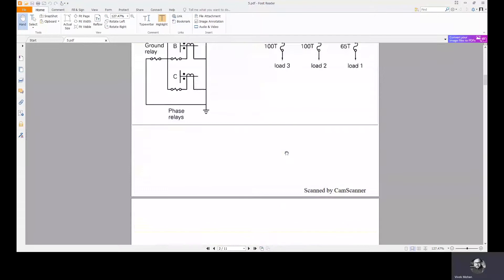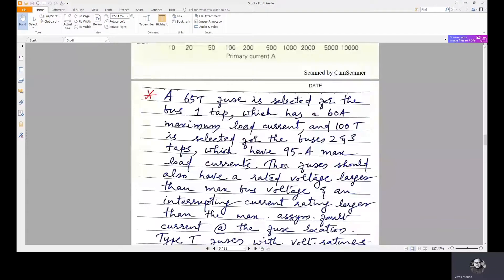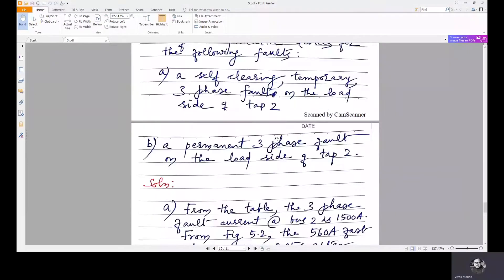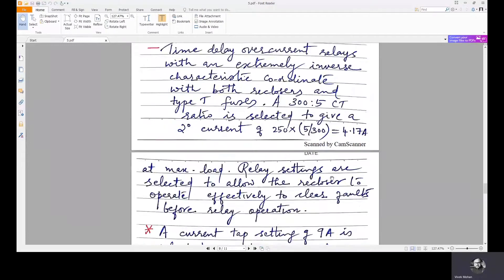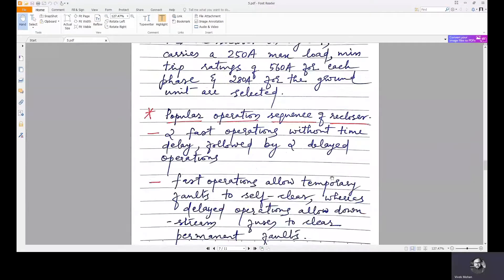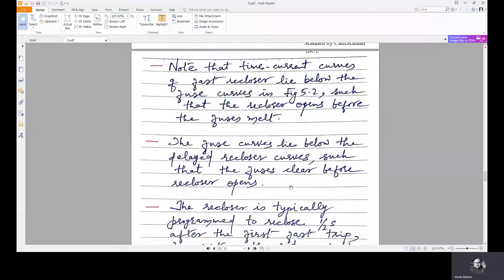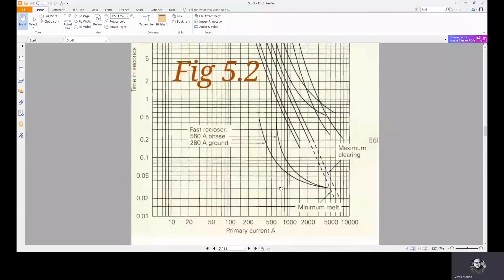In the second case, it is given that it's a permanent three-phase fault on the load side of tap 2. The current is the same — the tap 2 three-phase fault current is again 1500 amps, but this time it's a permanent fault. We will again go to the characteristic curve, and again at 1500 amps.